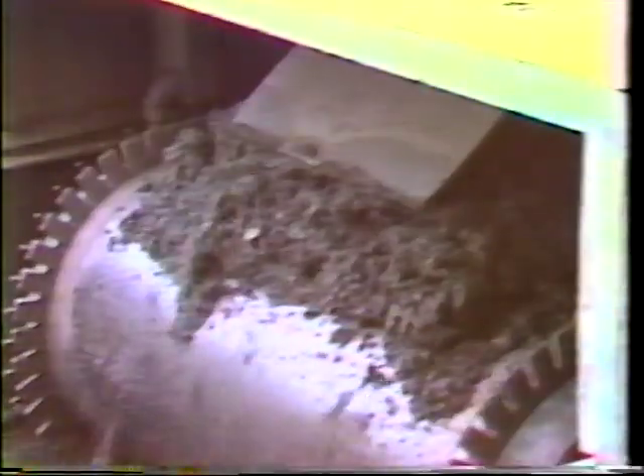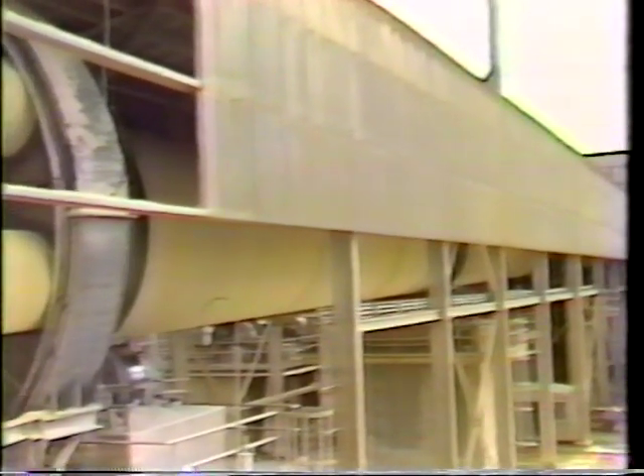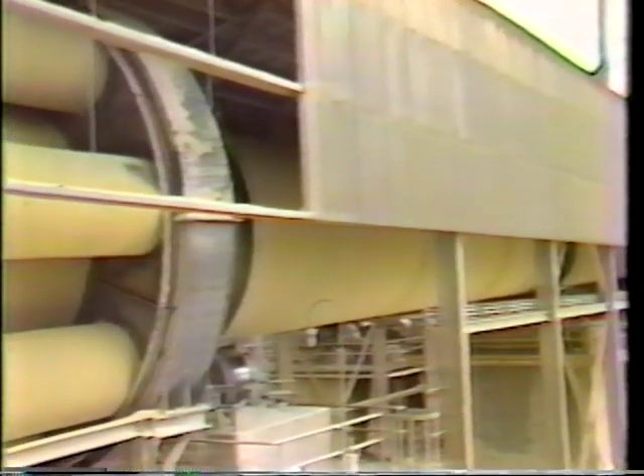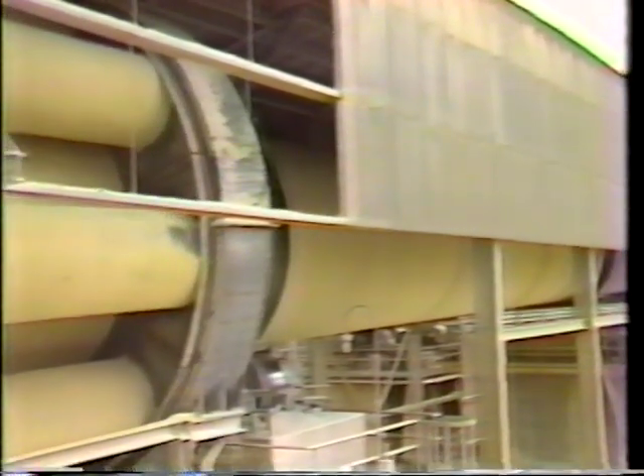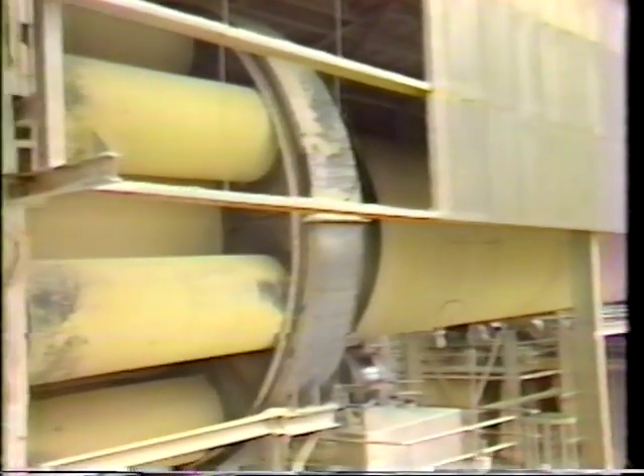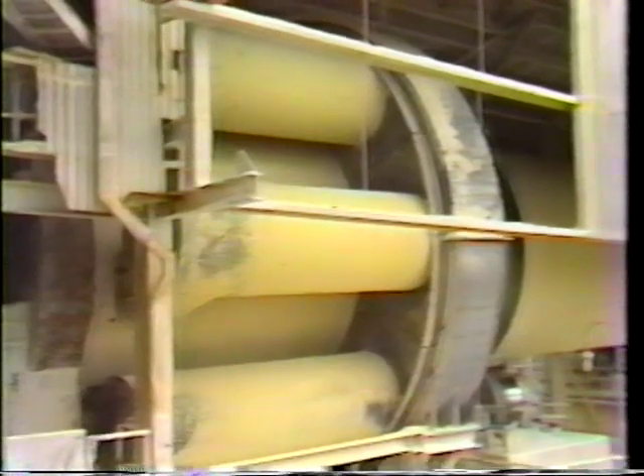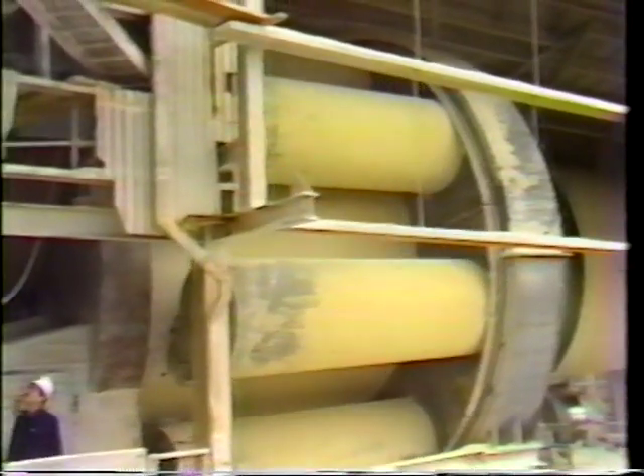Coke offers several advantages for use as a lime kiln fuel. The primary advantage is cost savings when compared to natural gas and number 6 fuel oil. The high heat content of petroleum coke also adds to its attractiveness. Coke usually runs about 14,000 BTUs per pound.